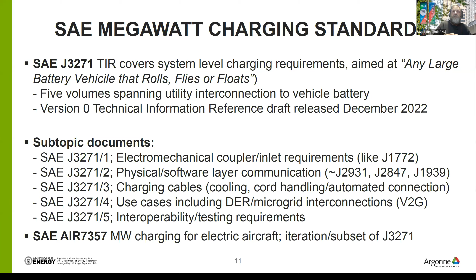So some people say, I see circles and dots, what do they do? Well, obviously the biggest pins on the top are the power pins. They're 20 millimeter diameter. And again, they're able to carry 3,000 amps continuous. You can see the little guards in the middle are fingerproof, so you can't stick your finger there and touch any hot surface, and they're interlocked, so it would never be live.